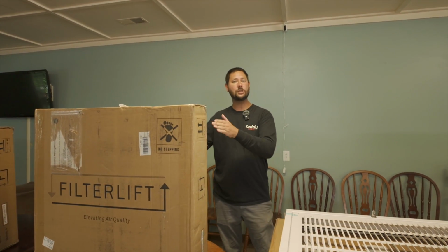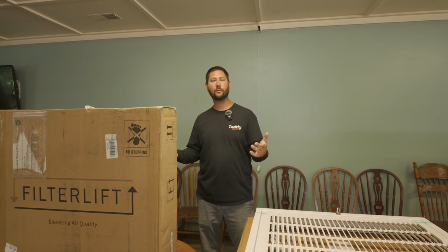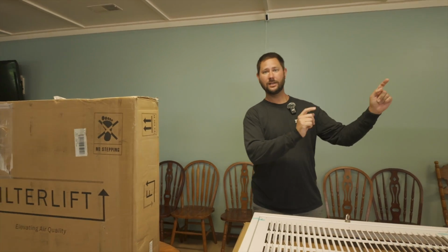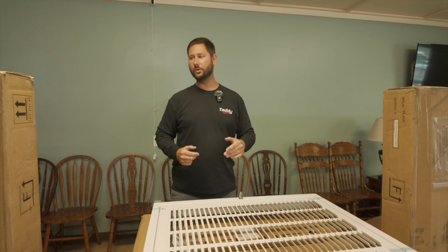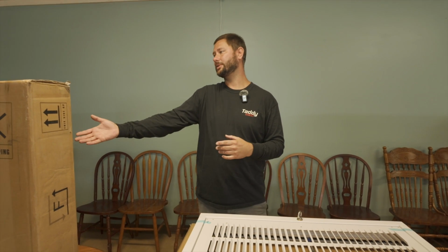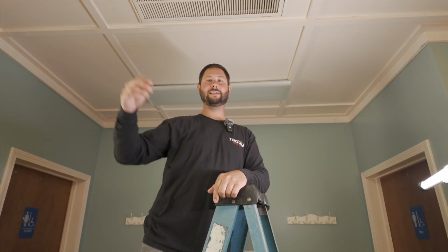Now you also can do different grills for different equipment. So let's say you have a 4-ton unit. You could do 2 20 by 20s instead of doing the 20 by 40. You could have a 5-ton unit with 3 20 by 20s, but that would be more filters that you have to replace. Some residential houses or businesses may have a filter grill in the ceiling, and it's not fun getting on a ladder to replace that filter.